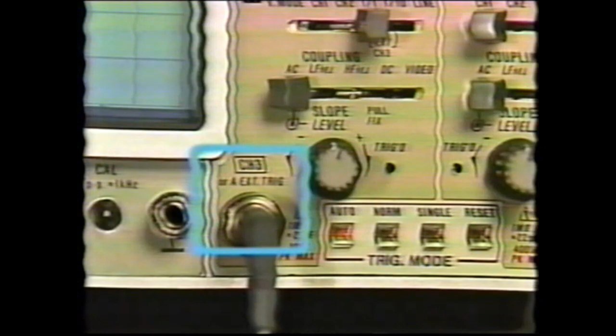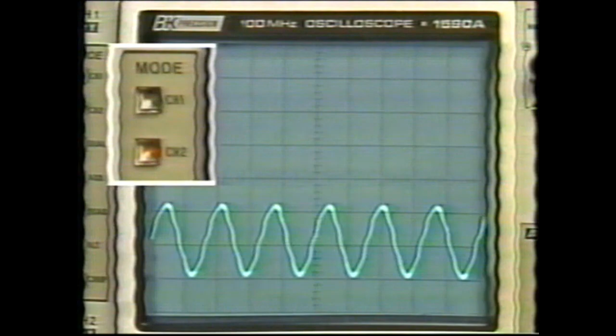The A source switch selects the signal to be used as the sync trigger for the A sweep. On this oscilloscope, it includes V mode, channel 1, channel 2, 1:1 and 1:10 external channel 3, and the line position. In the V mode, each waveform being observed becomes its own trigger signal and is dependent on the vertical mode selected. For example, when the vertical mode is changed from channel 1 to channel 2, the triggering source is changed from channel 1 to channel 2. In the line position, the trigger signal is derived from the input line voltage, 50 or 60 Hertz.